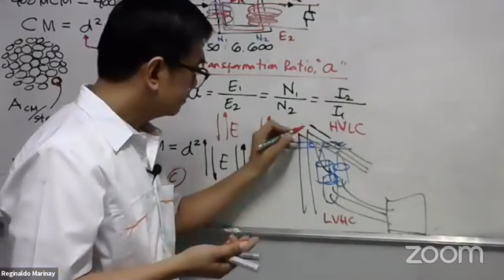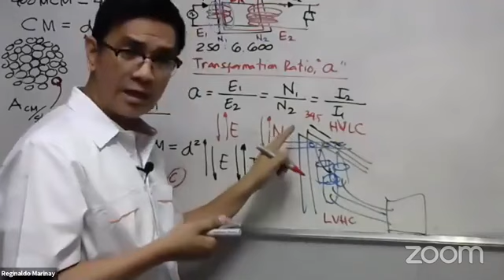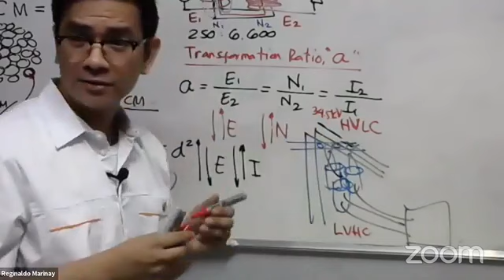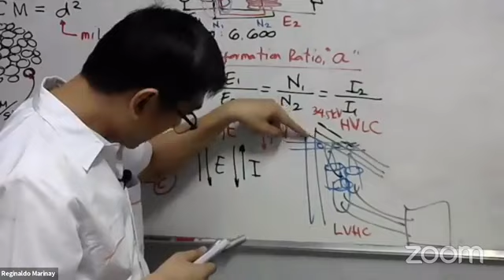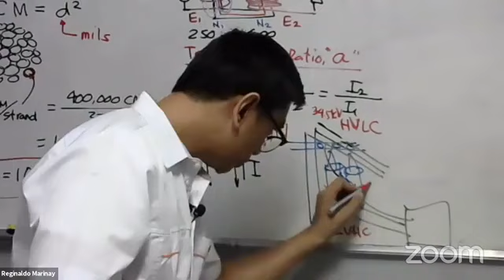One sample voltage used by the utility company is, let's say, 34.5. Oh sir, that's very low. No, it's in kV, kilovolts, not volts, meaning it is 34,500 volts. That is the line-to-line voltage on the primary side. Then on the secondary side, that is approximately 230 volts, which is the nominal voltage of the utility.